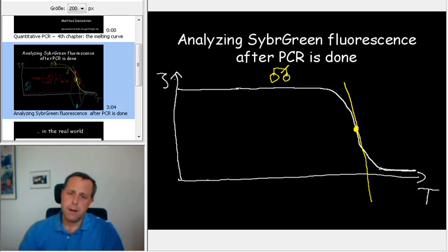Well typically you try to find out at what temperature the intensity curve was turning. This is a bit difficult to understand like that but let's assume you are riding a bicycle. So here is a bicycle and you're riding this bicycle along your curve. What will you need to do in order to go along this curve? Well you will need to tilt in that direction and if you then go further with your bicycle you will need to tilt to the other direction in order not to fall. But at one point in between and that's exactly this point here, the turning point, there you will be in an upright position and that's what you typically define as your melting point.